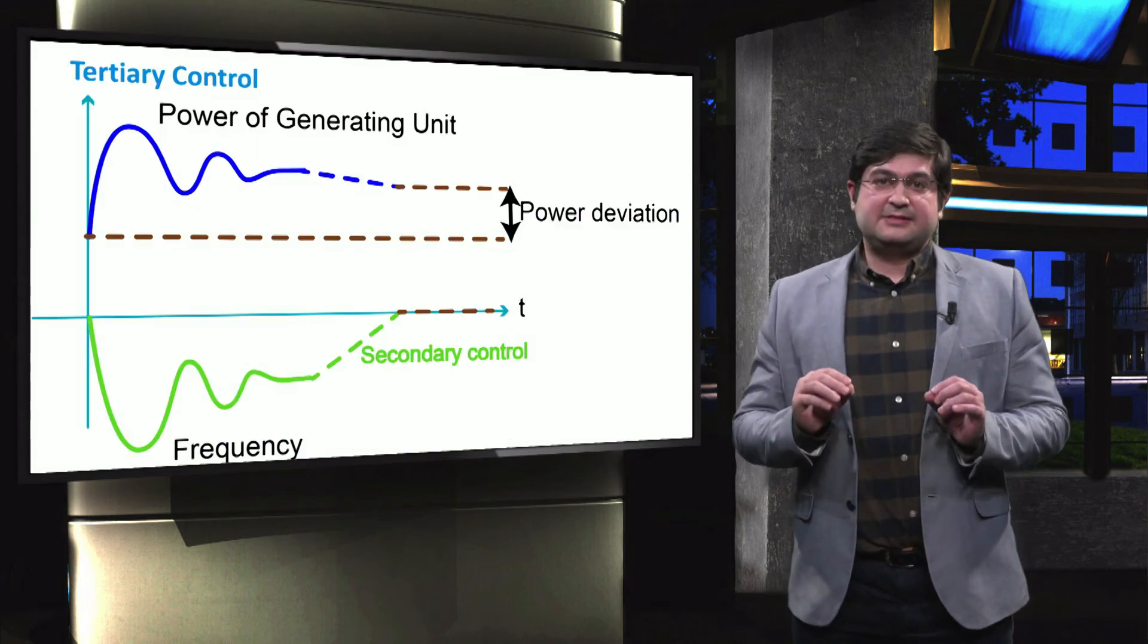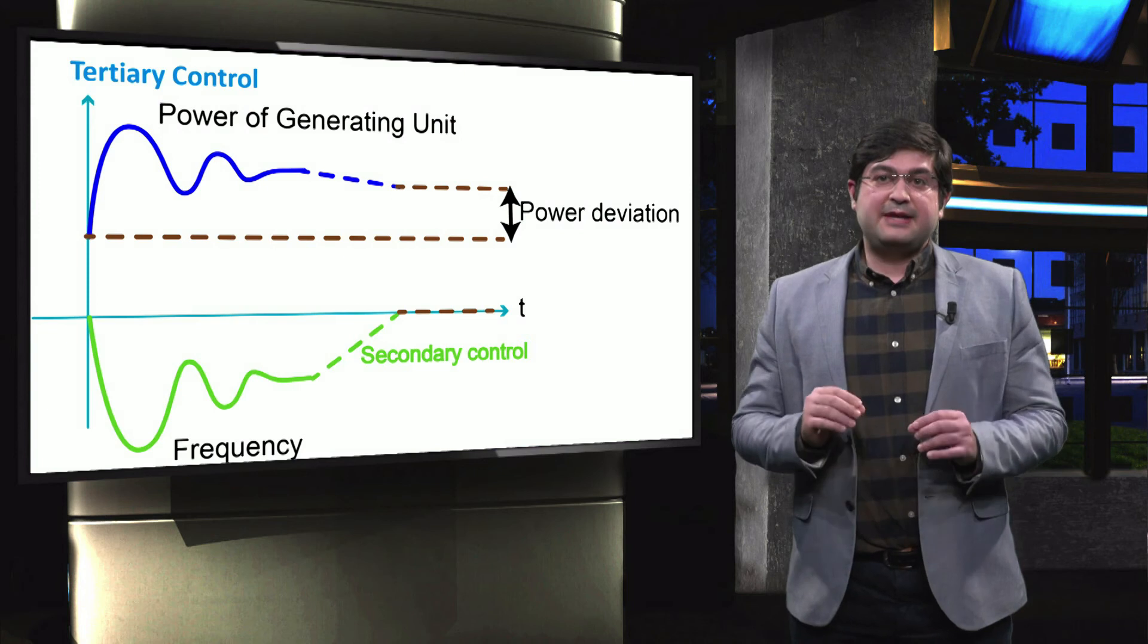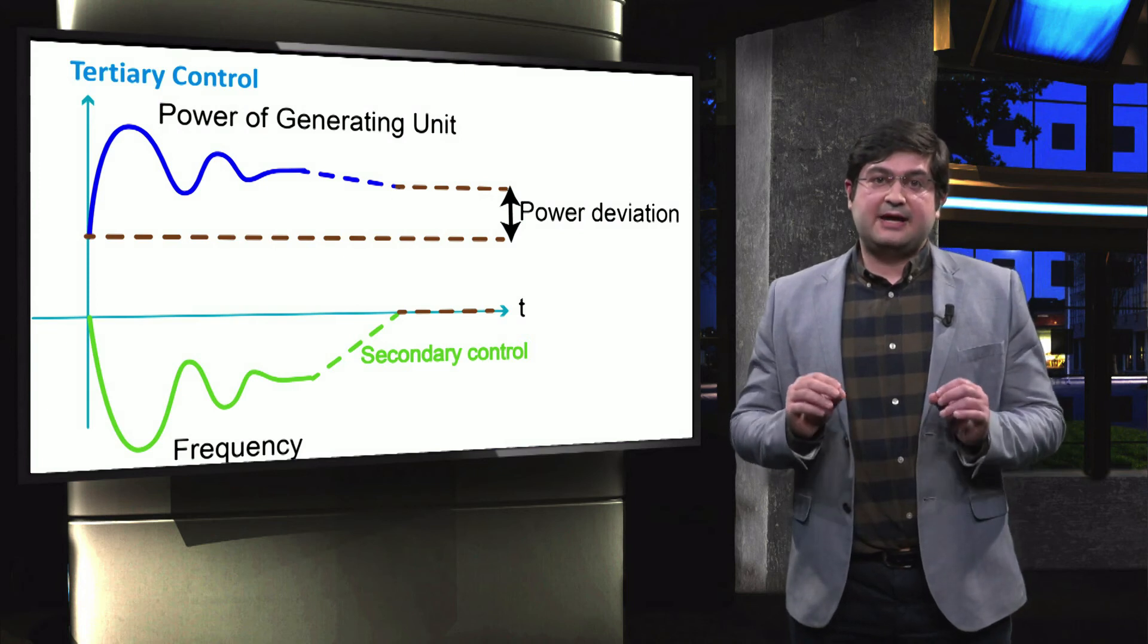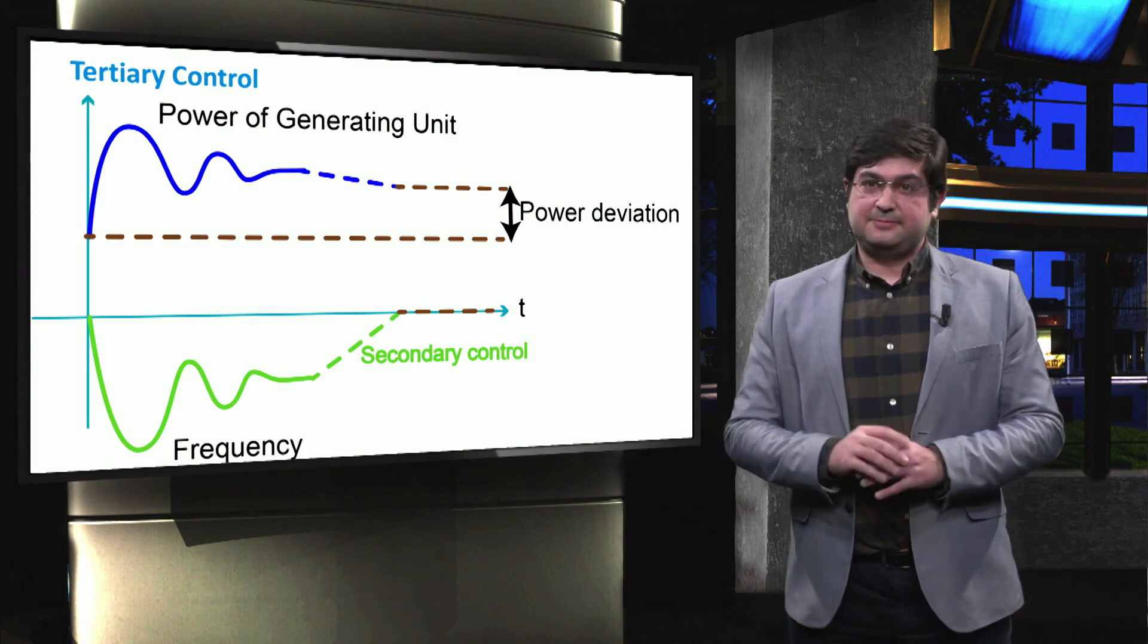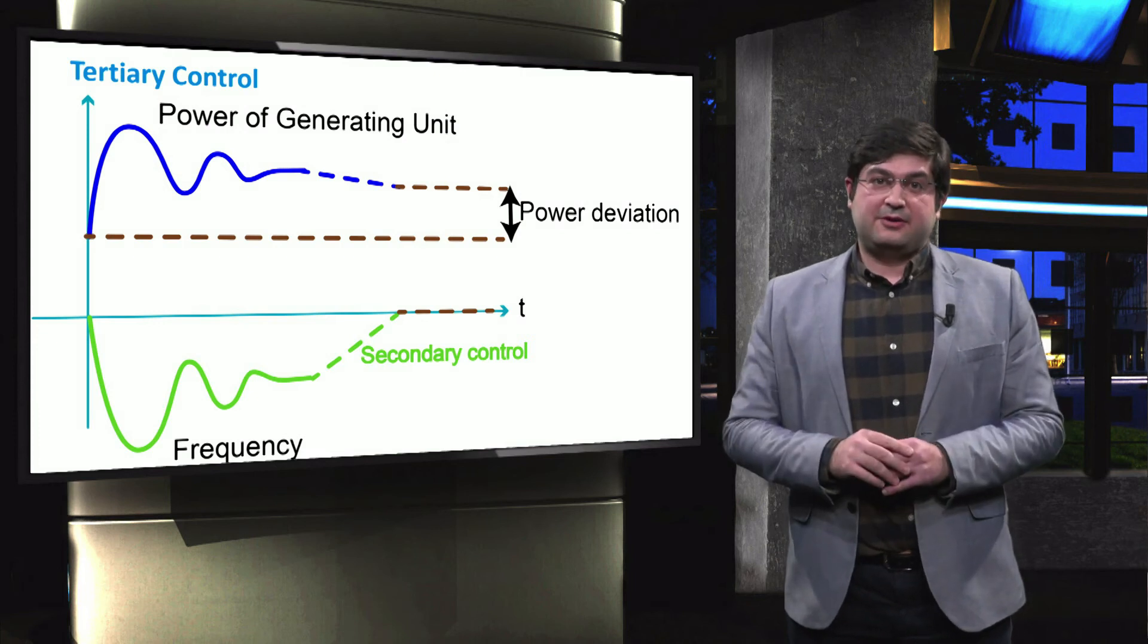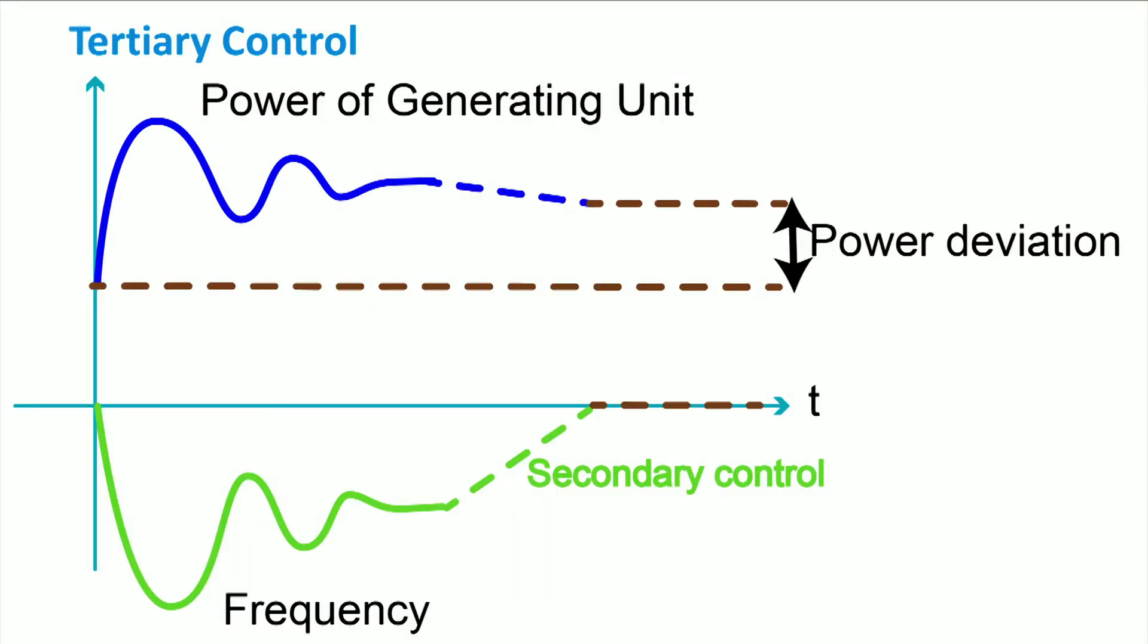So far, we discussed that the secondary control helps maintain the level of the frequency at the nominal values after the disturbance, as it is shown in the green curve. To achieve this, however, the power set points of the generating units need to be adjusted during the disturbance, as it is shown in the blue curve. Therefore, there will be steady state deviations for the power of the generating units before and after the disturbance.